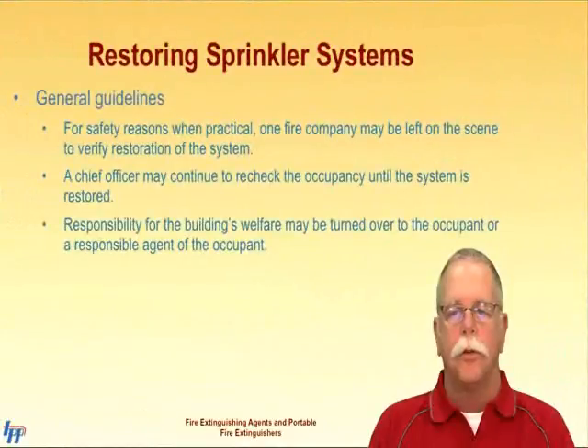It is most desirable for the fire sprinkler system to be fully restored prior to the fire department leaving the incident scene. However, with no credentialed fire protection technician on scene, this may be impossible. Establishing a fire watch or returning to the scene to recheck may be an acceptable practice depending on the jurisdiction. It is important to remember that due to liability, fire department personnel should not change sprinkler heads or take other action in an attempt to restore the system unless authorized by your agency.